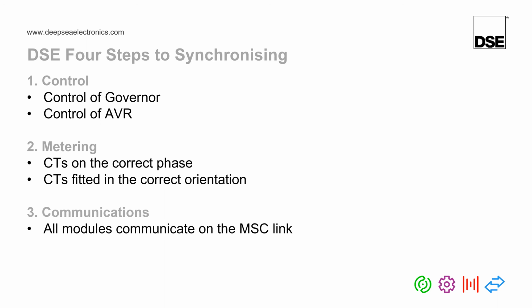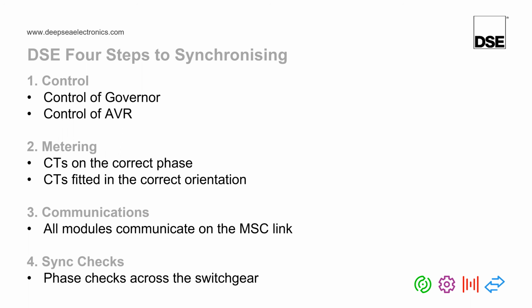The third step is to make sure that all the modules are communicating correctly on something that we call the MSC link. The MSC link is a digital communications link between all of the controllers. And finally, we need to do some phase checks across the generator's switchgear to make sure that there hasn't been any strange wiring problems. It's worthwhile noting that to do the 4 steps, you will need some form of laptop or PC and the DSE configuration suite to perform them.